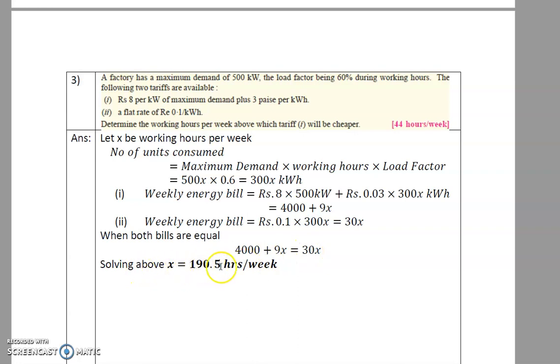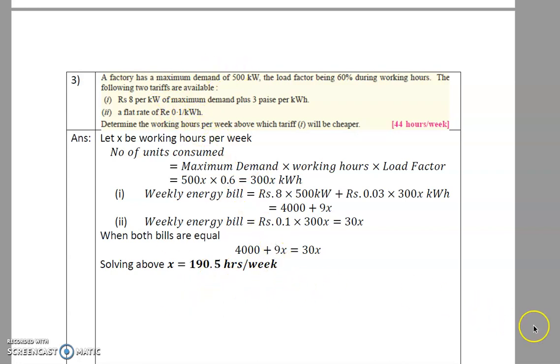Solving: x = 4000 / 21 ≈ 190 hours per week. If the industry works more than 190 hours per week, Tariff 1 is cheaper than Tariff 2. Below this, Tariff 2 is cheaper. Likewise, you can apply this method to similar calculations. Thank you.